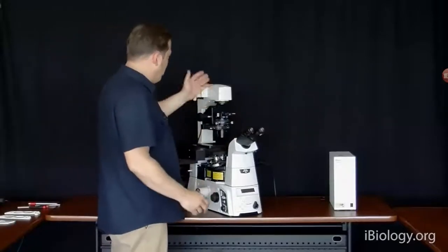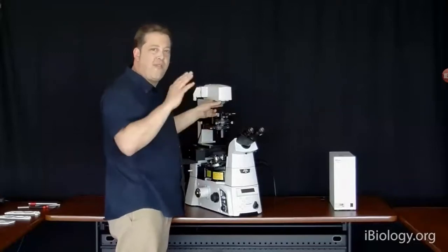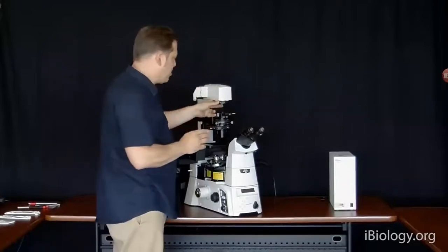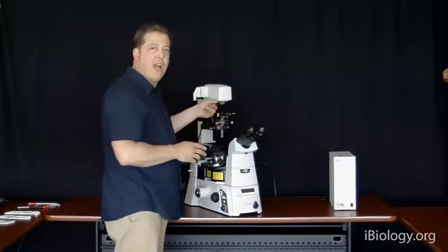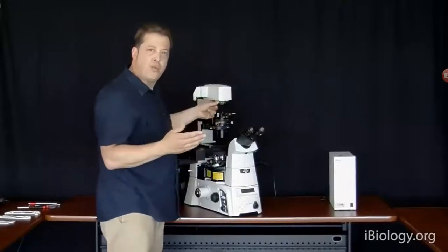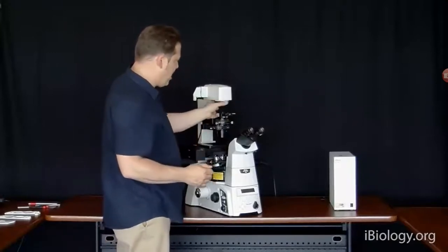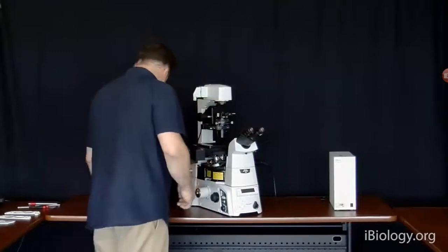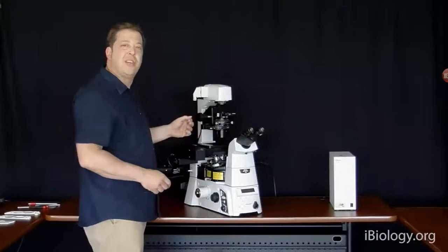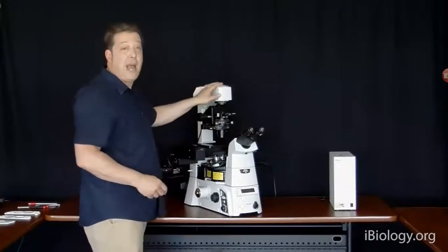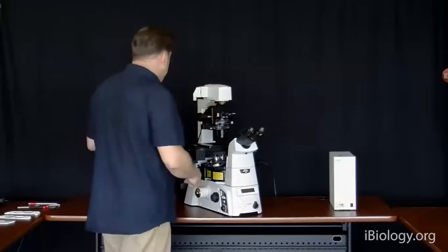So we come through here. We then have a lens here, which is called your field lens. That's actually in the first field plane of the microscope. And you have an aperture here called the field aperture. Now that's the aperture that we would close when we're doing Köhler illumination of the microscope, and it's controlled right here. I guess I should really call it a field iris, since I don't want to confuse the aperture planes and image planes. So the field iris is here on the microscope.